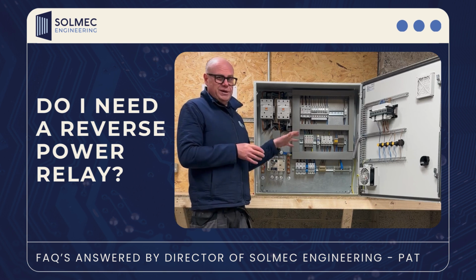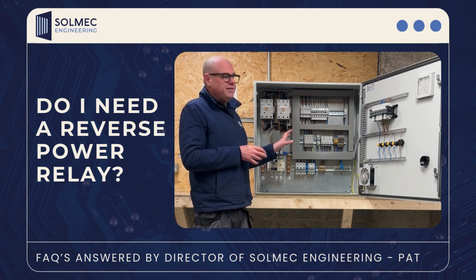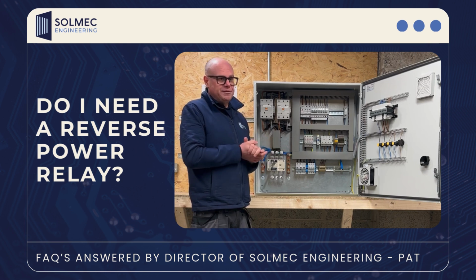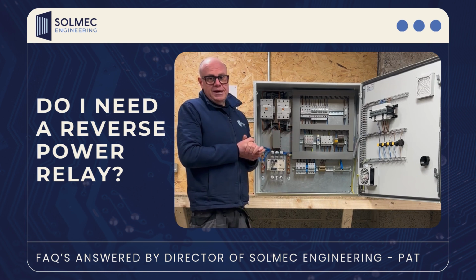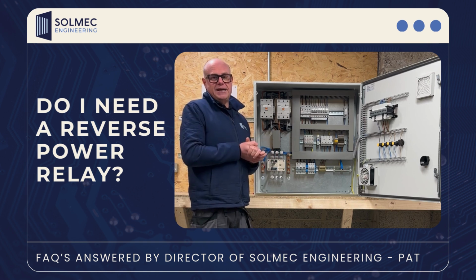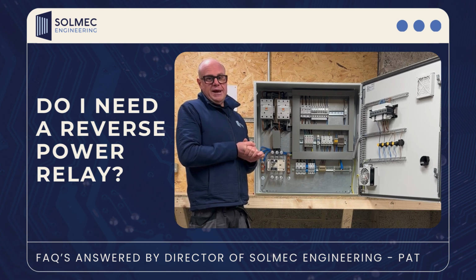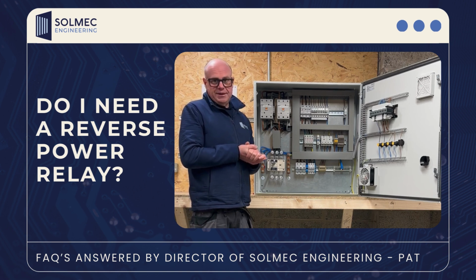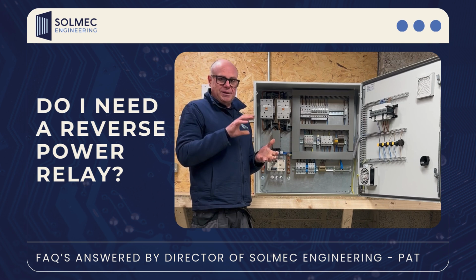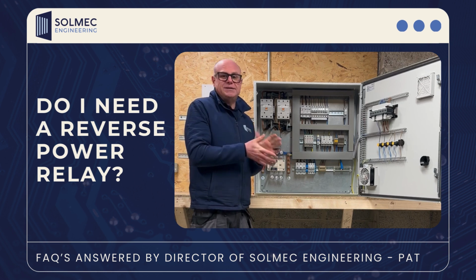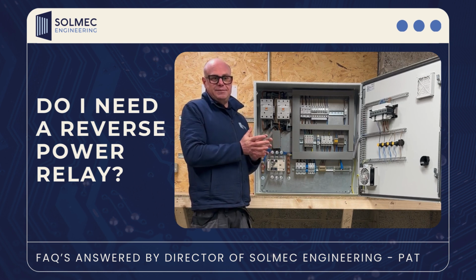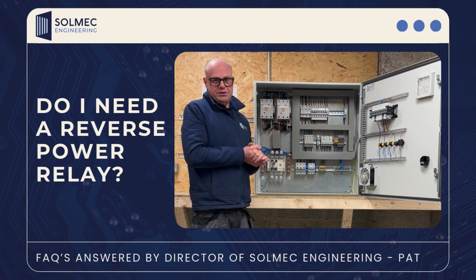The reason why you don't need the reverse power relay between 50 and 200 kilowatts in the small scale generation G99 protection is because the ELS systems that exist on nearly all of the inverters are accepted as doing the same thing: the same conditions that can be simulated through the ELS systems on the inverters is the same action that a reverse power relay does.